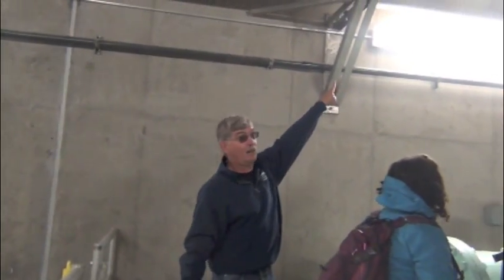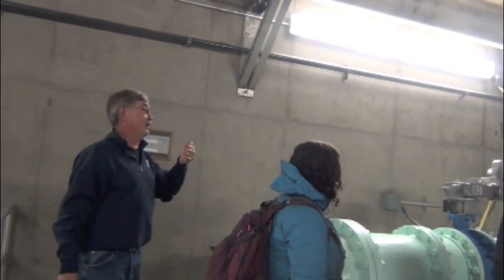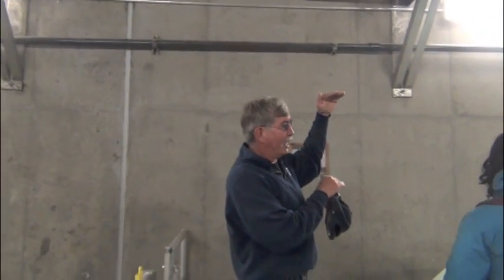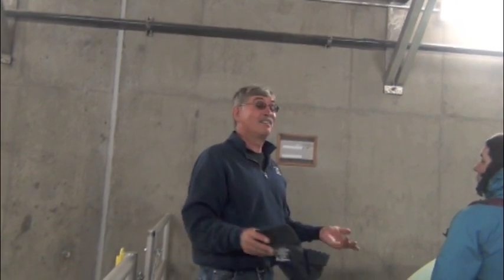After it goes in, it comes out through the decanter. When the floating decanter up in the corner of the basin opens and it wants to decant, this valve will open down here. It knows the level in the basin and does a mathematical equation. It has 72 minutes to decant. It will decant over that 72 minutes, keeping an equal flow going out of the basin, which allows it to go equally across that UV channel, so you don't have a big rush of water. It's actually mimicking the flow through the treatment plant system. It's a special design for this treatment plant.